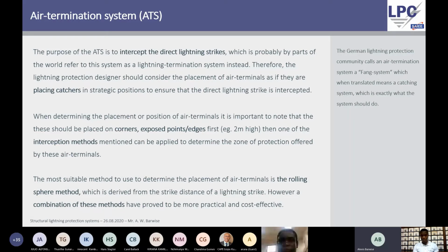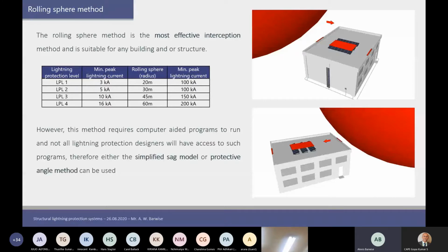So we look at some of the practical points. Here we see that the standard guides us to say these catching systems or these air terminals should be placed on corners. Any exposed points, so sharp edges like a facade or a pitched part of a roof, right? And this is a great concept to say, let's start by placing air terminals on these exposed points, corners, on edges. Select a certain height of the air terminal and then apply some simplified mathematical models, such as the rolling sphere method, which is derived from the standard, as well as perhaps even combining the rolling sphere method with a protective angle method to make a more practical, cost-effective example. And let me show you what I mean.